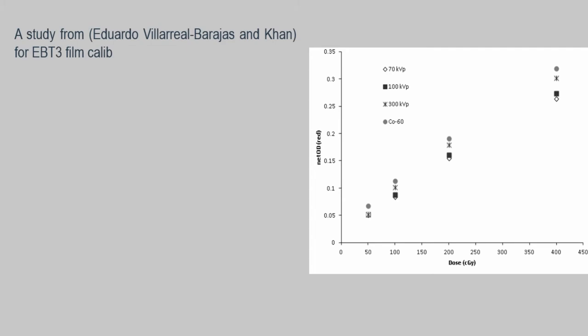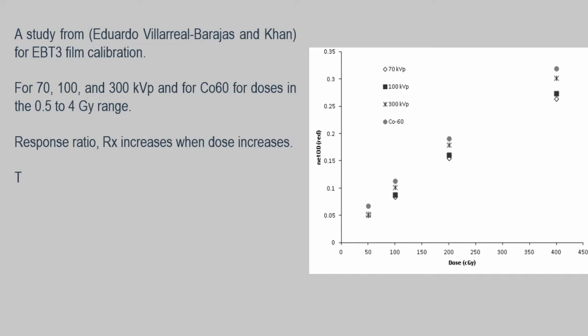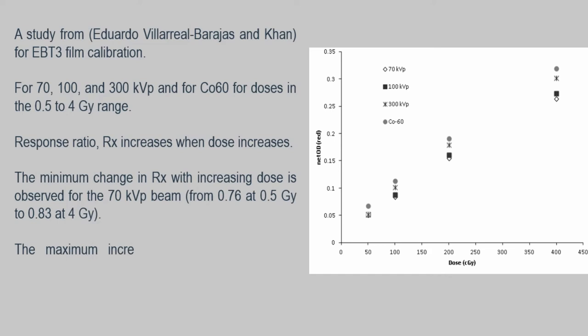Another study was done for the calibration of EBT3 film. The study was done for photons with energies of 70, 100 and 300 kVp and for Cobalt-60 in the dose range of 0.5 to 4 gray. From the graph, it can be seen that the response ratio Rx increases when dose increases.